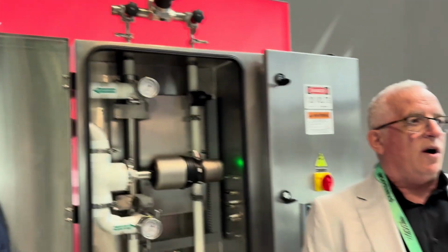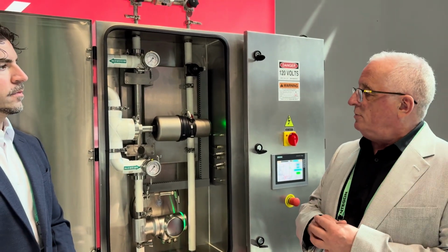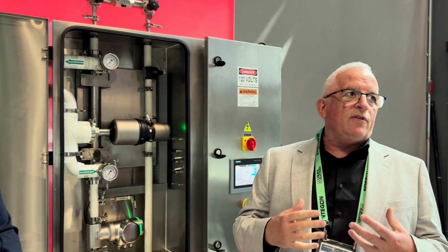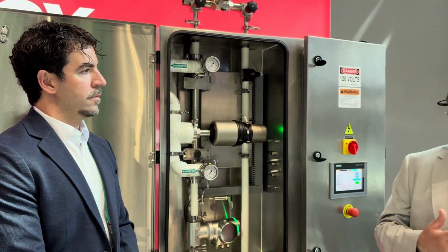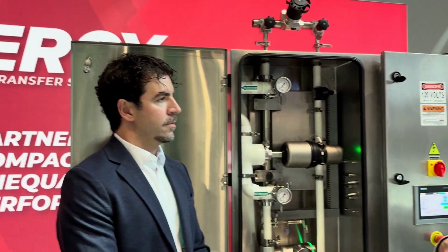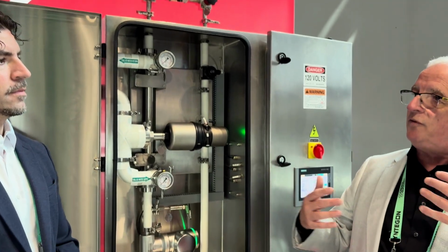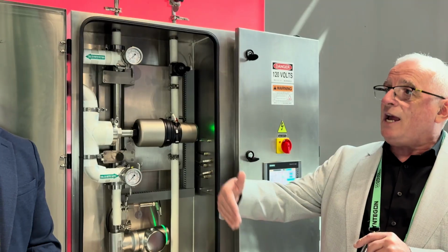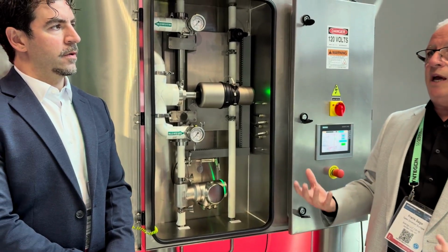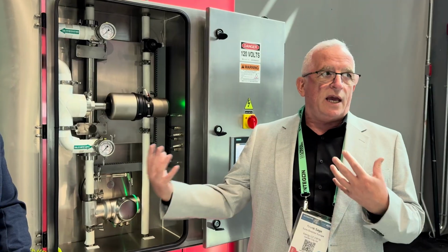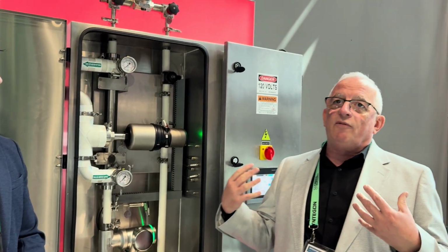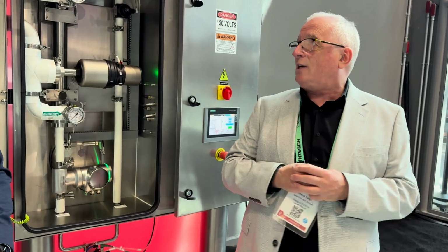We get specifications from major pharma. Our largest customer in the world now has bought over 40 systems. Every WFI distribution and dispense project that they have, they tell us we want zero ambient pipe work, and we want no WFI waste, and we want instantaneous availability of variable flow and temperature WFI simultaneously without pressure drop loss 24/7. So that's a pretty high bar that we have to reach. But we do reach that, we reach it consistently, and when the customer takes the time to engage with our engineering team, we really provide an excellent solution for this most critical utility in pharmaceutical manufacturing. And I think that's where our partnership comes in.